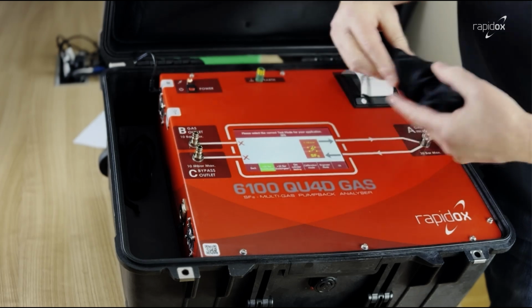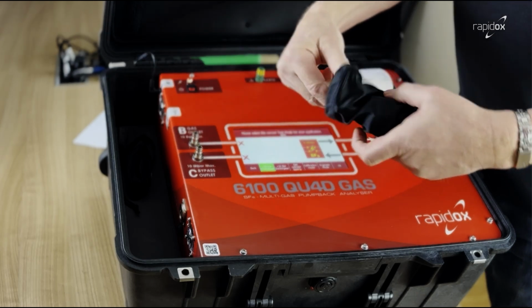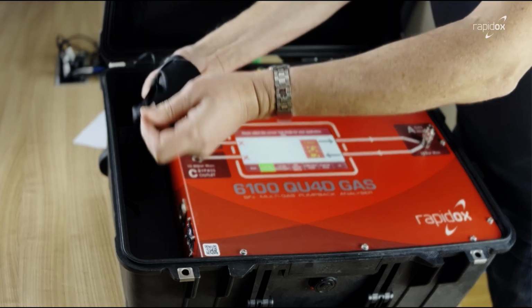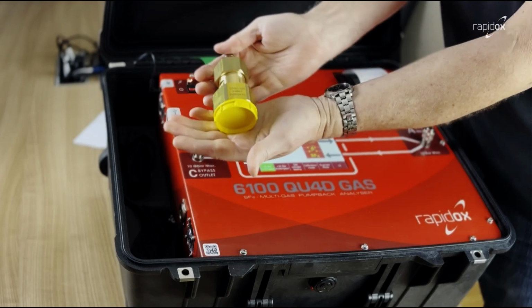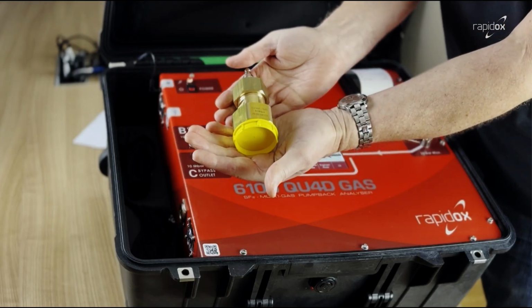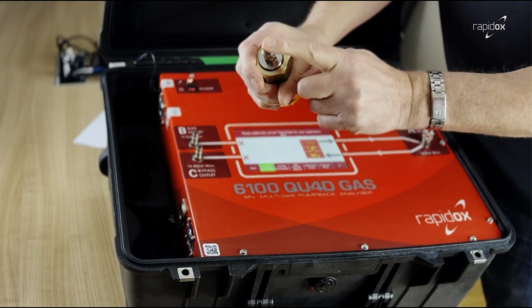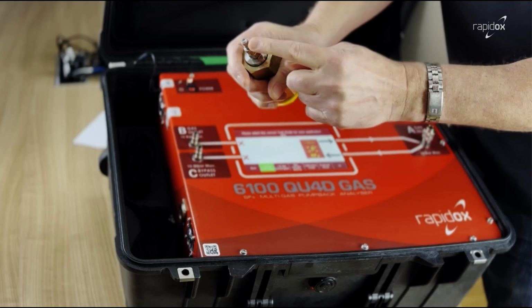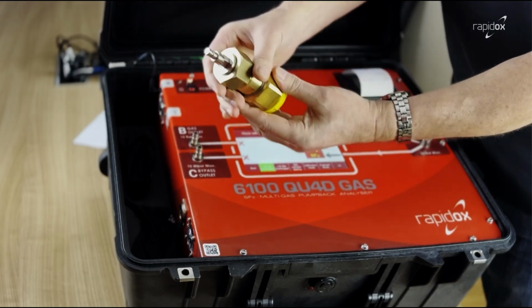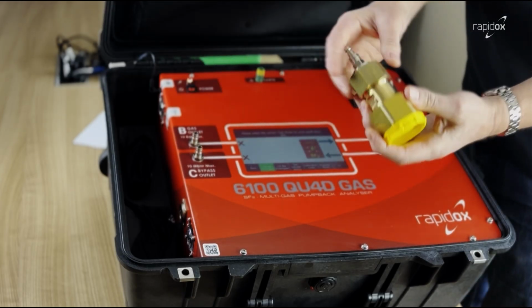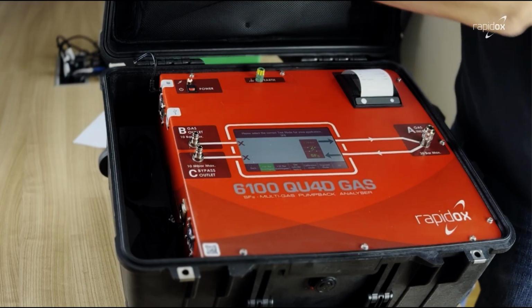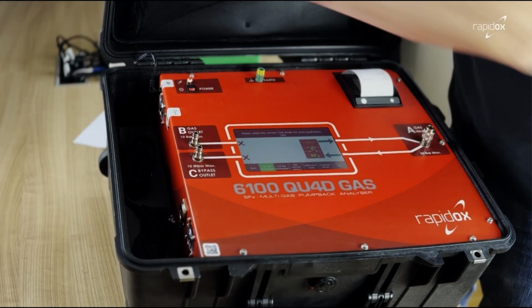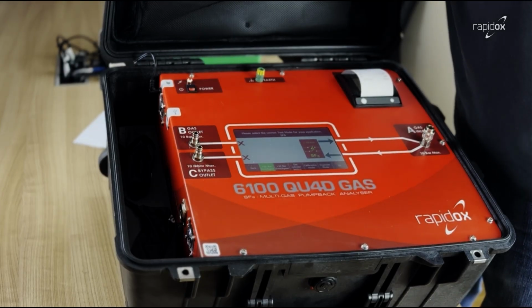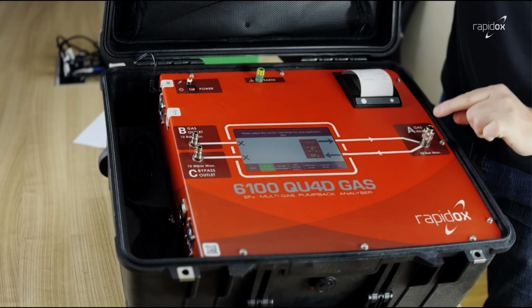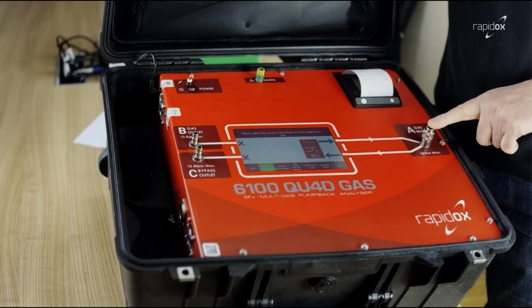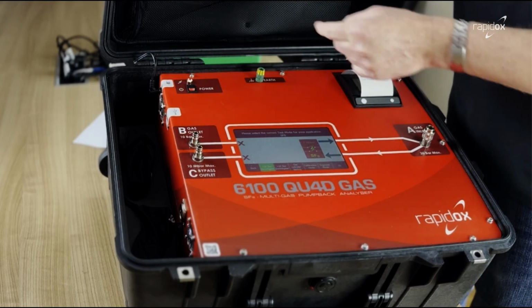We do supply them in a camera bag just to stop them getting scratched. So this is a DN20, and you can see that it's got a male Rectus on it. So with the hose fitted, this would be attached over onto the circuit breaker. The hose would connect on here with the female, and then we would feed the hose round using the male into the analyzer. Okay, there you go.